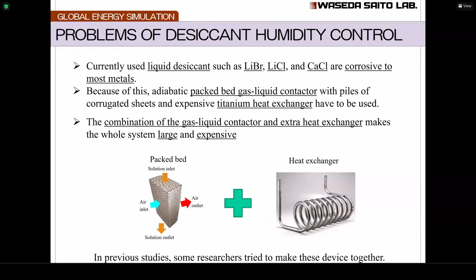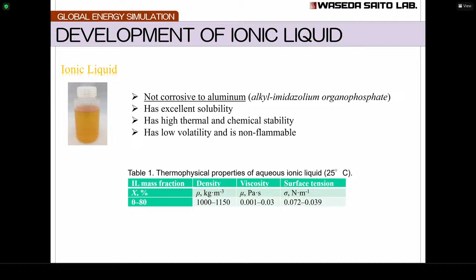But recently, we developed a completely new liquid desiccant, an ionic liquid, with some German chemical companies. This liquid is not corrosive, has excellent solubility, has high thermal and chemical stability, has low volatility, and is non-flammable. That's why it is a very good liquid desiccant that we developed. So we can use aluminum, and that's why we can make many kinds of systems. This system is a combination system of packed bed and heat exchangers.